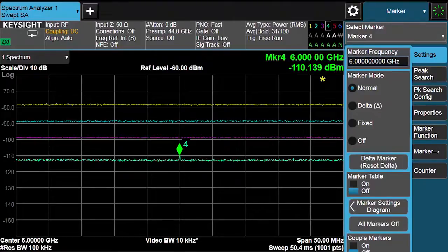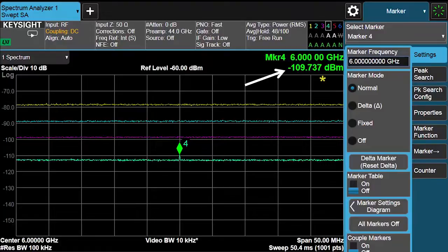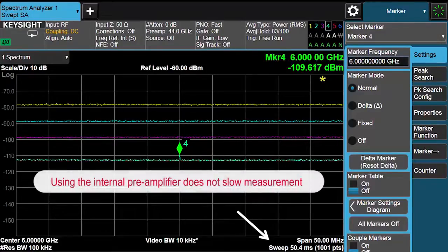So I'll go ahead and turn on the internal pre-amp, and we'll see the tremendous improvement in sensitivity. So now you can see there's a low level spur popping up at marker 4. We're getting a reading on that marker of minus 110 dBm. Notice that when you use the internal pre-amplifier, the sweep speed doesn't change. Using the internal pre-amplifier does not slow down your measurement.